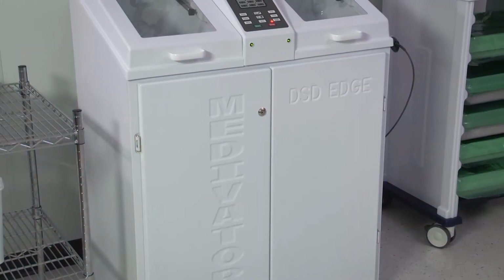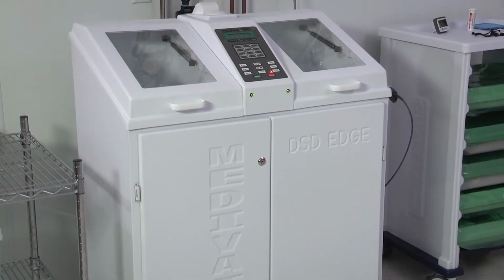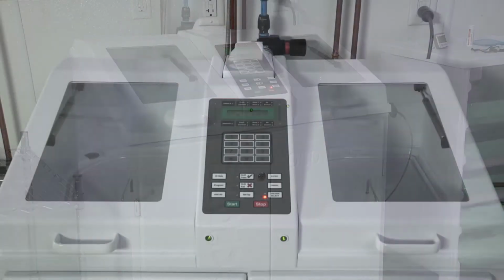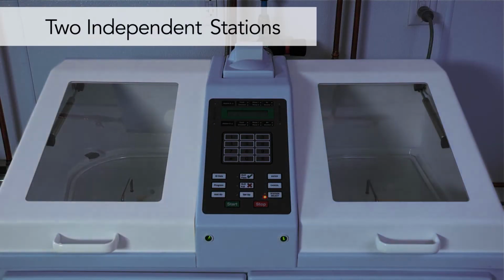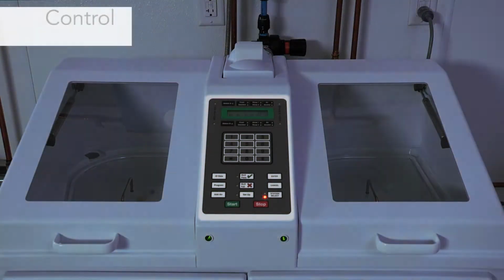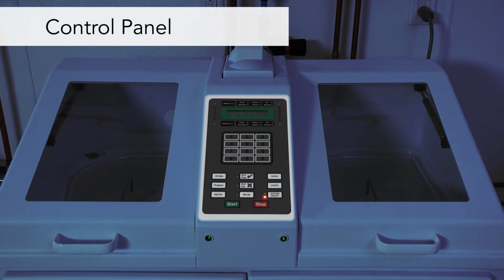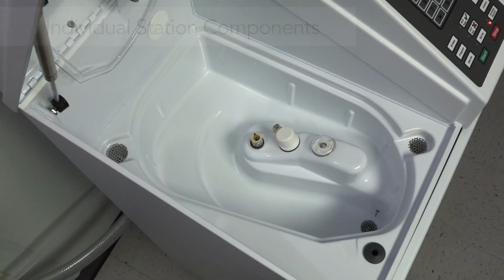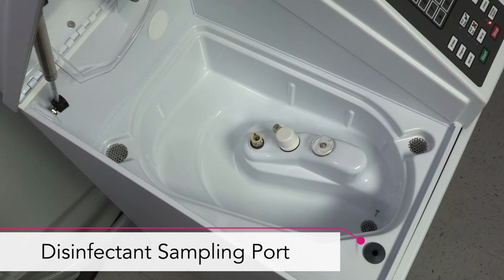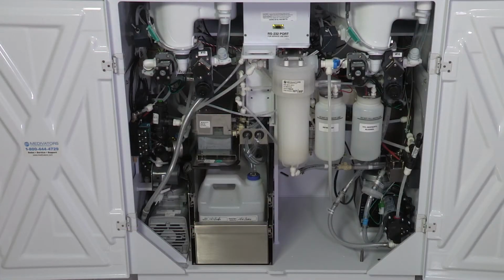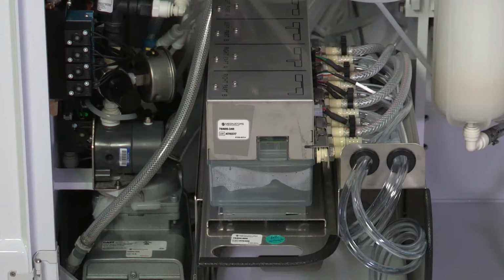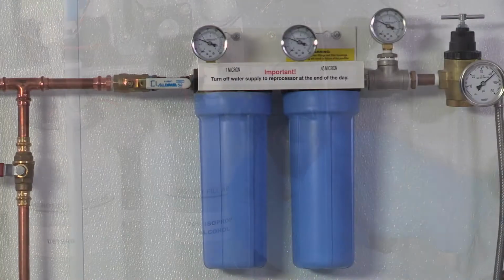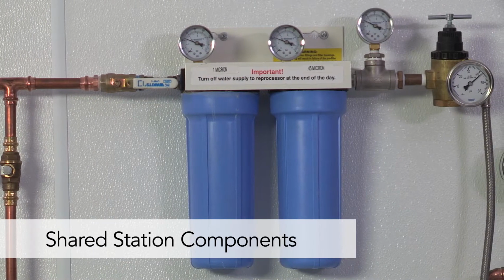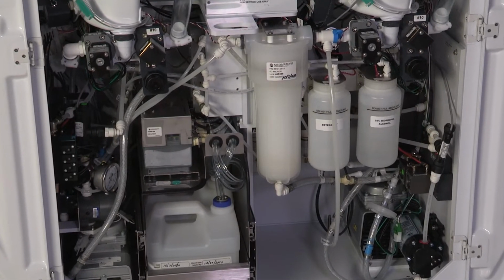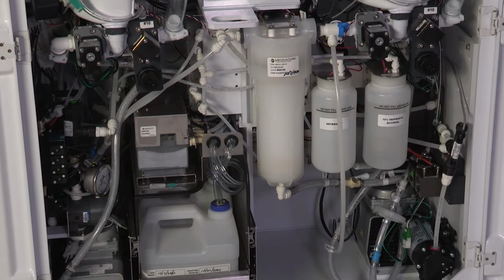Let's take a closer look at the features and components of the DSD EDGE Reprocessor. The DSD EDGE Reprocessor features two independent stations. Both stations are operated by a single control panel. Each station has its own basin with disinfectant sampling port, its own system of fluid lines and valves, its own pump, compressor, dosing chambers, air filter, and disinfectant filter. Shared components include the water filters, alcohol and detergent reservoirs, Rapicide PA disinfectant, and air tank.